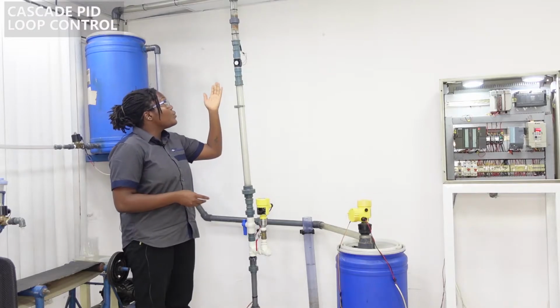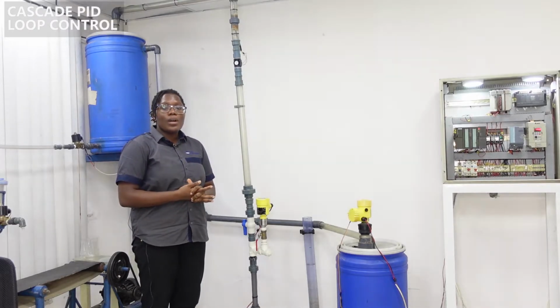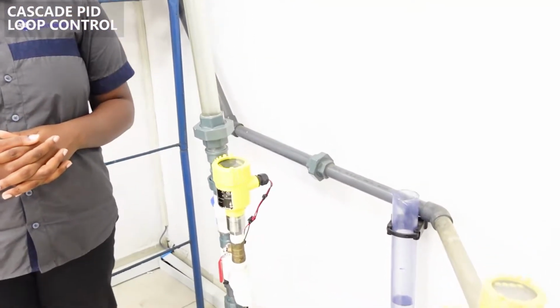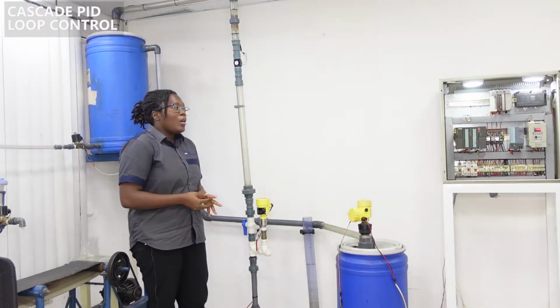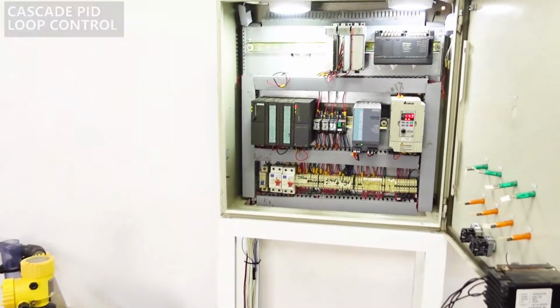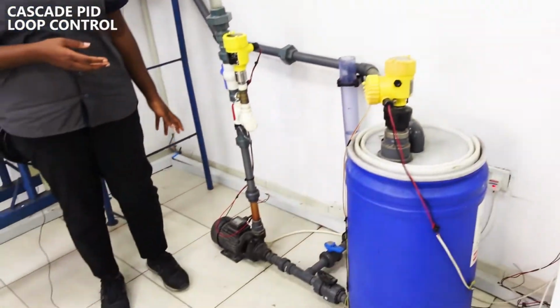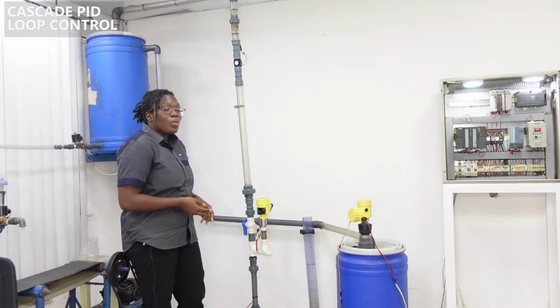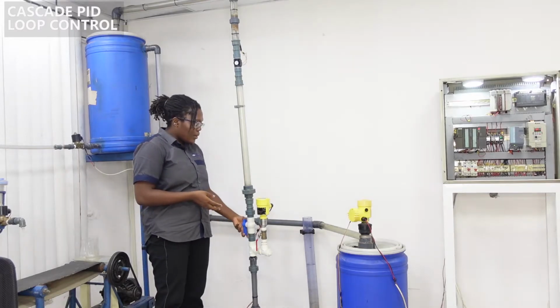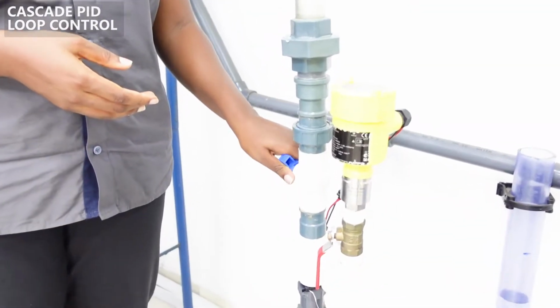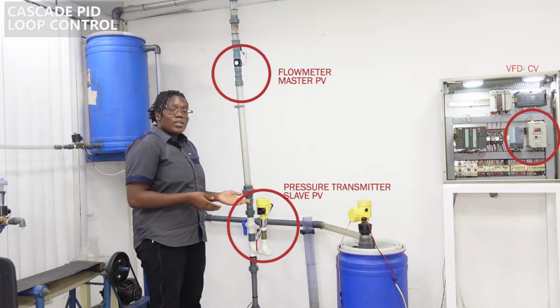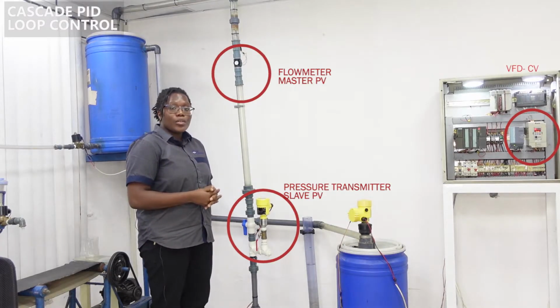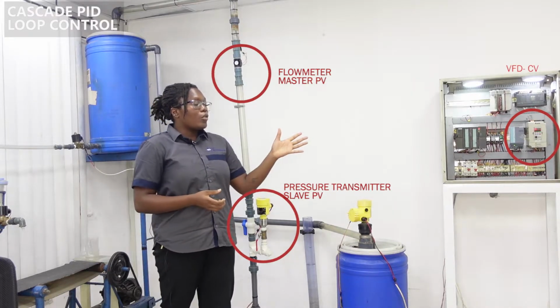variable to act. In this setup, we have a flow meter, which will be the process variable for our master loop, and a pressure transmitter, which will be the process variable for our slave loop. Our control variable will be our variable frequency drive, which controls a three-phase pump. We will cause a disturbance to this system by closing and opening this valve. The pressure transmitter would detect the change in pressure and cause the control variable to act.